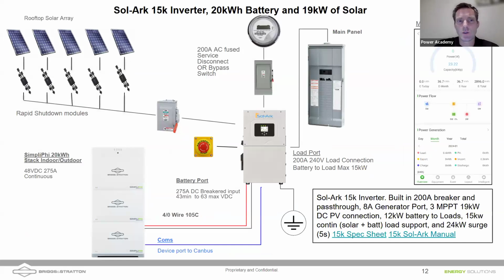You might have DC solar on the roof. We're showing those rapid shutdowns there. You're showing a disconnect for the solar. Now that Sol-Ark 15K does have that DC disconnect built into the side. That's the switch you can see in the middle on the left. We are showing emergency stop. That emergency stop will shut off the rapid shutdown. It'll also shut off all the loads of the inverter as well.